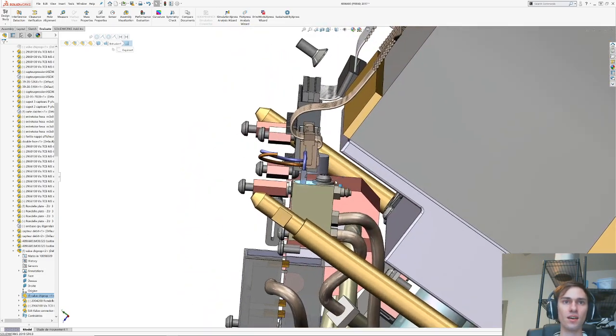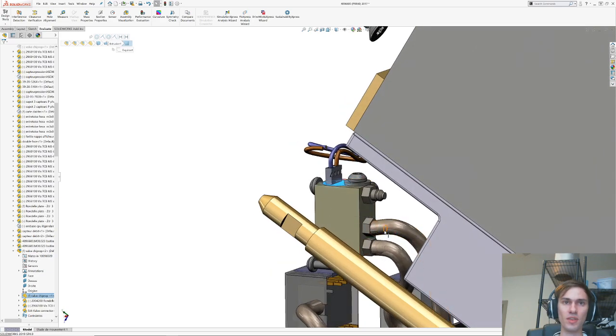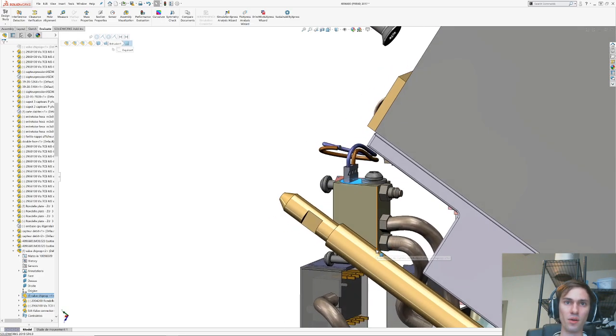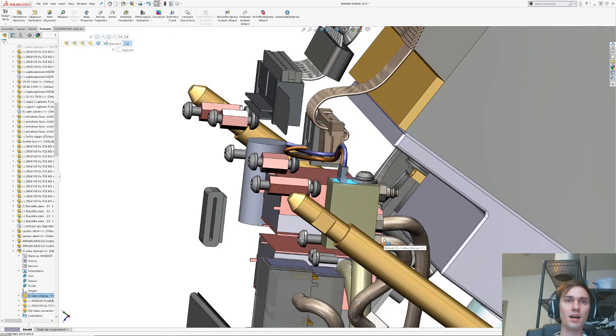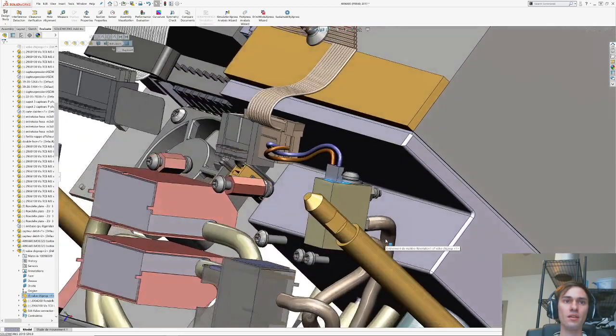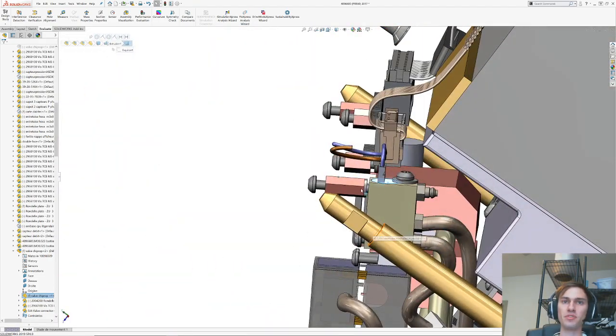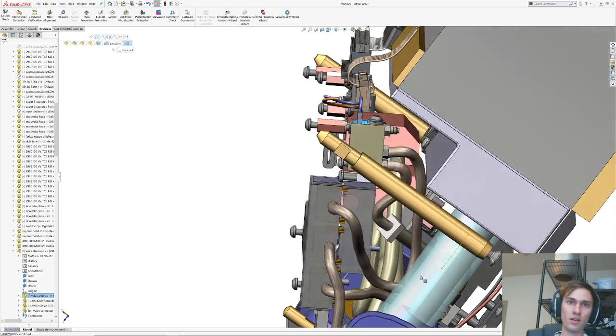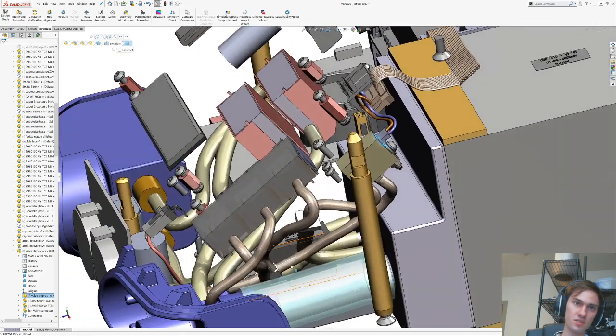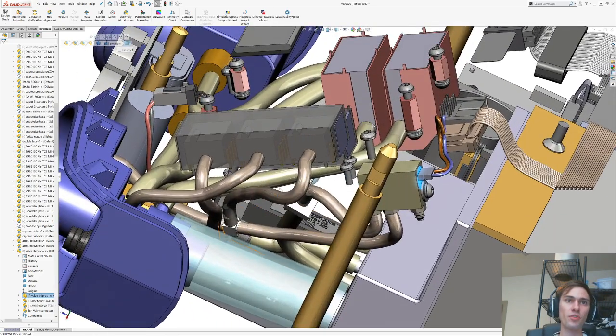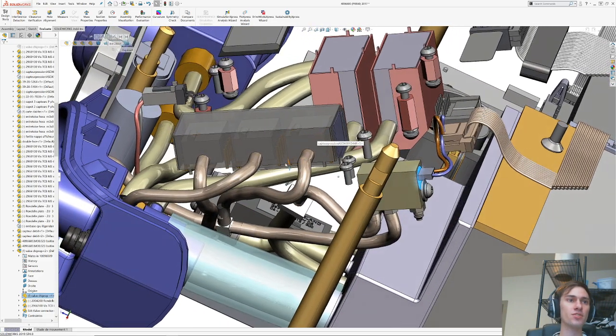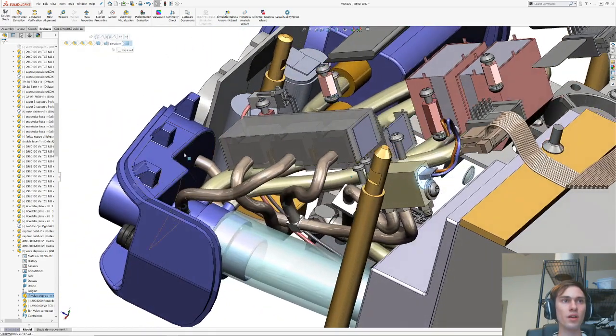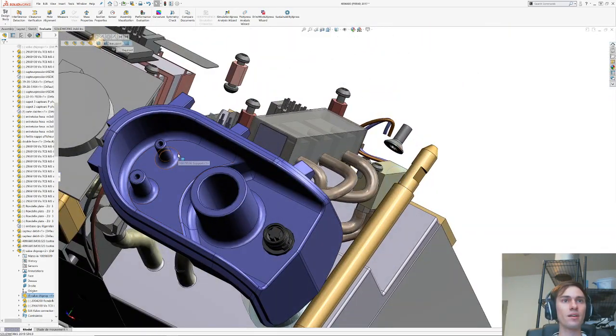And it looks like it has NC and NO ports. So this is going to be the outlet. This would be the normally closed inlet, and this would be the normally open inlet. I think that's how that works probably. Or maybe I've got the reverse of that, but something like that. One of these will be the normally closed, one of these will be the normally open, and then this will be the outlet. So then it takes the outlet and it goes to this splitter here. And this splitter provides one pressure to a sensor on the control board, and the other one comes to here.